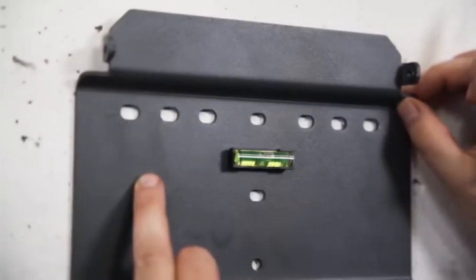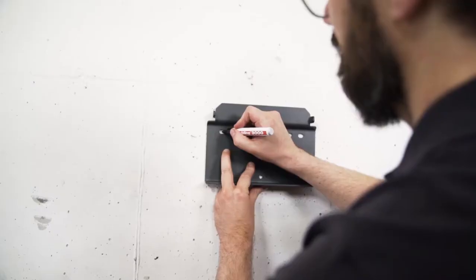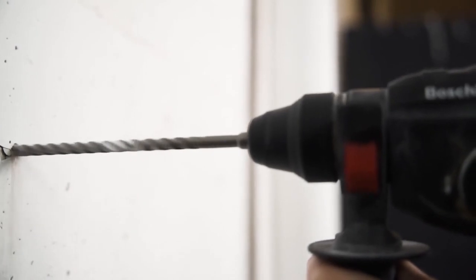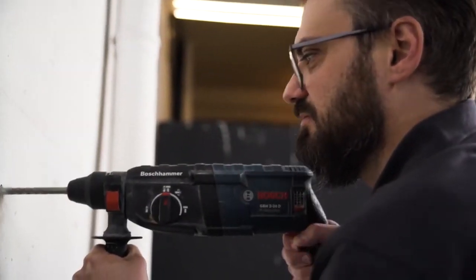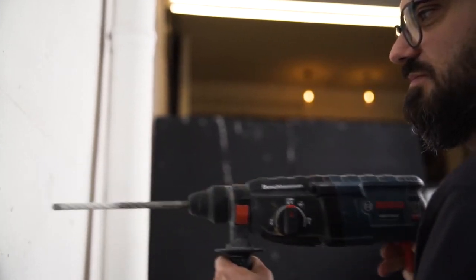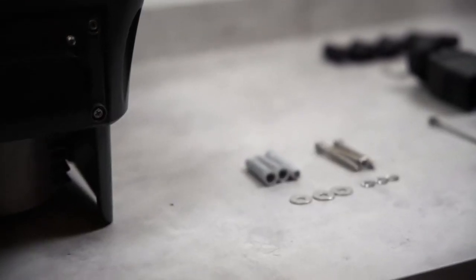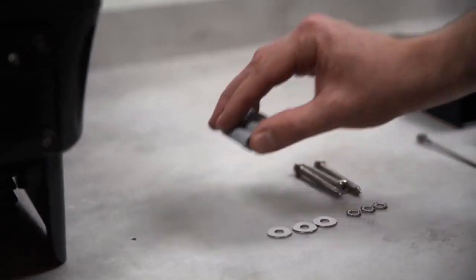Before you start drilling, you should make sure that there are no wires running through the wall that you could damage. Take your drill with the 10mm drill bit and drill at least 70mm deep into the wall at the marked points. The dowels for mounting the inverter on the wall are included in the delivery.